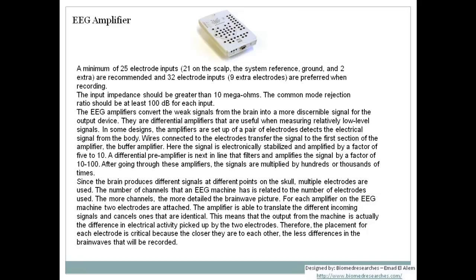With higher channel counts — 64 or up to 128 — the extended 10-10 electrode placement system is used instead of the standard 10-20 system. More channels yield a more detailed brain wave picture. For each amplifier, two electrodes are attached; the amplifier translates differing incoming signals and cancels identical ones. The output is the difference in electrical activity between the two electrodes — specifically the potential difference between the active and reference electrode — making precise electrode placement critical.